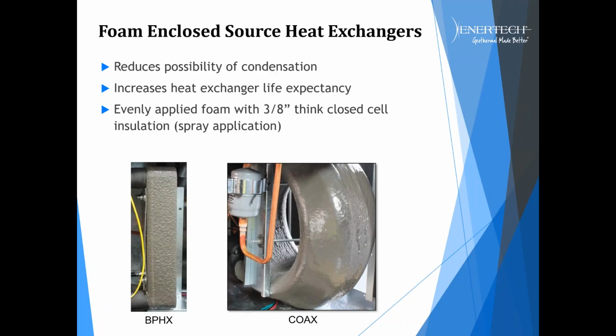And anything that Enertech builds that's going to be extended range or low temperature application, we're going to use a spray foam application on the heat exchanger just to prevent any type of condensation or corrosion on that heat exchanger. Whereas a lot of the industry has gone to a foam tape, which isn't an airtight seal, and of course the R value isn't as good. We've gone to a unique spray foam application. It's about 3/8 of an inch thick. Okay, and it's a very rigid foam. It's a 16-pound foam and very tough, very durable. You can see there it's very well applied and does a great job just to make sure there's no way we could ever have any condensation and corrosion happening on that heat exchanger. And that's, again, with the extended range or low temperature geothermal applications.